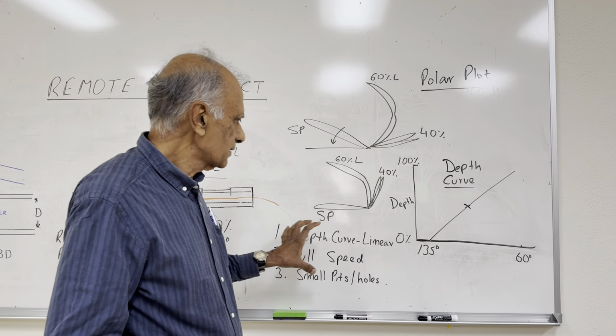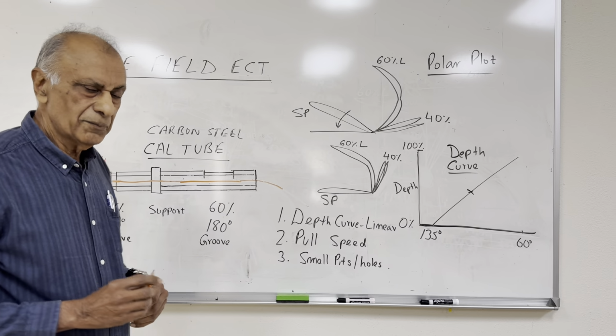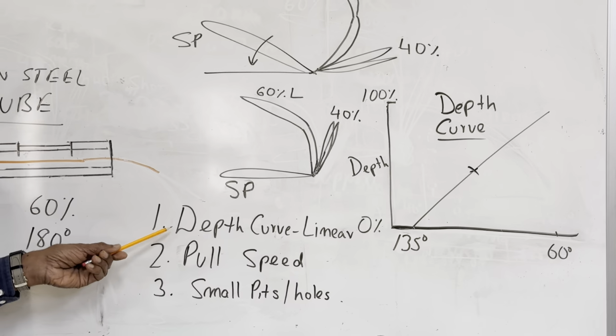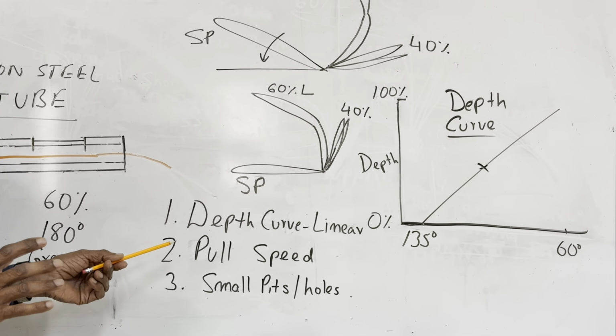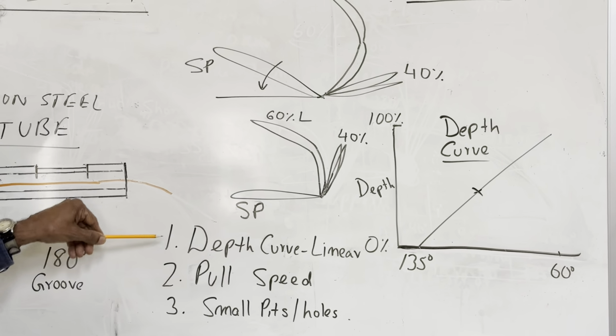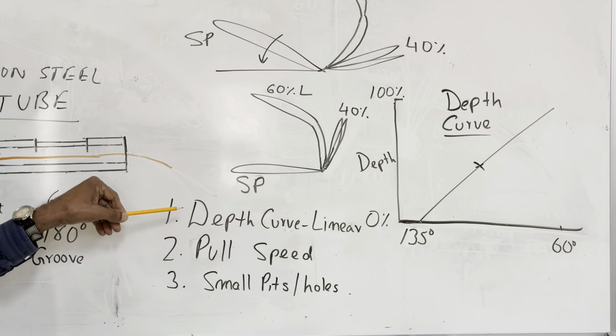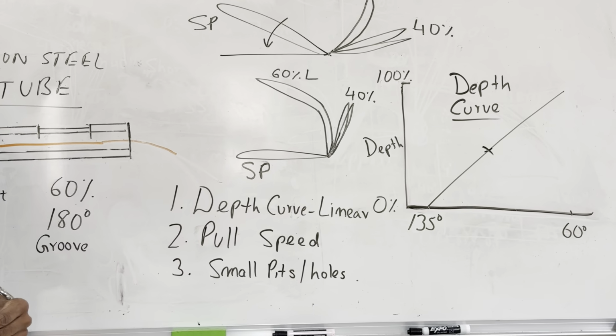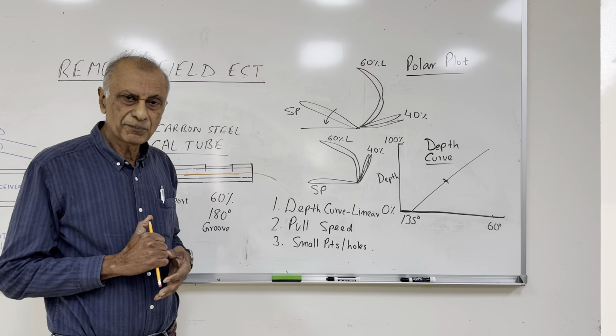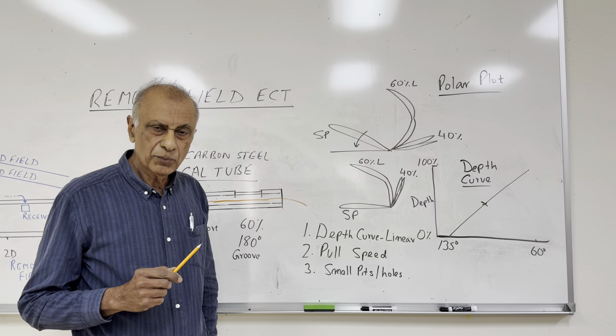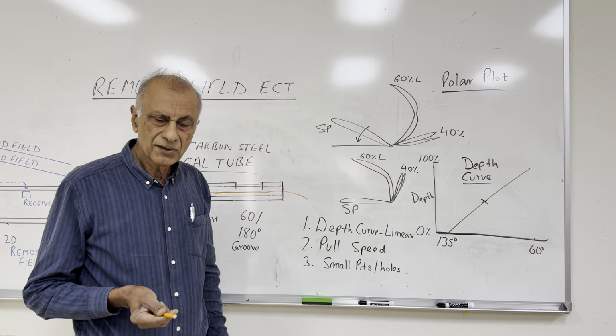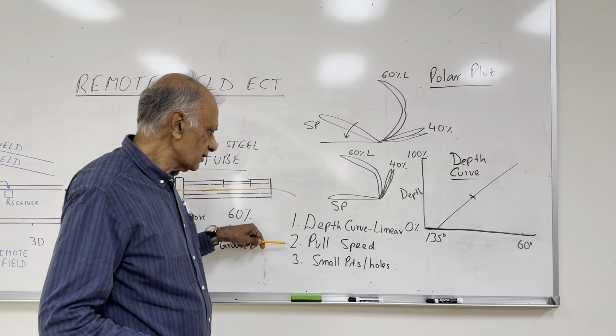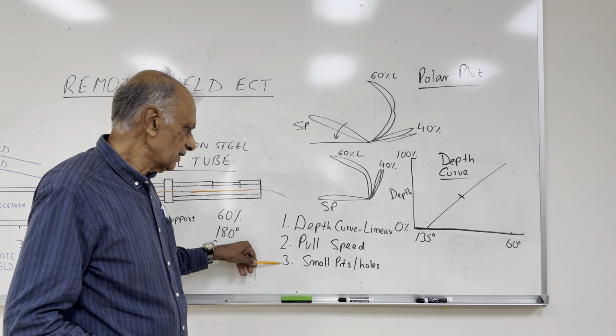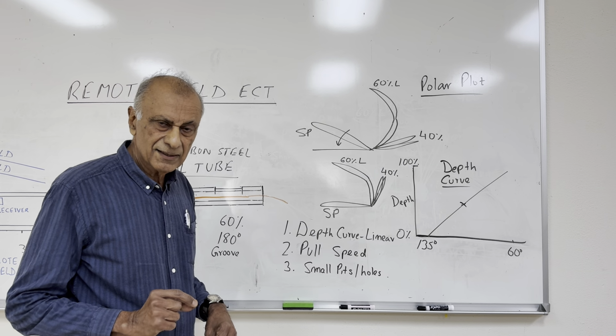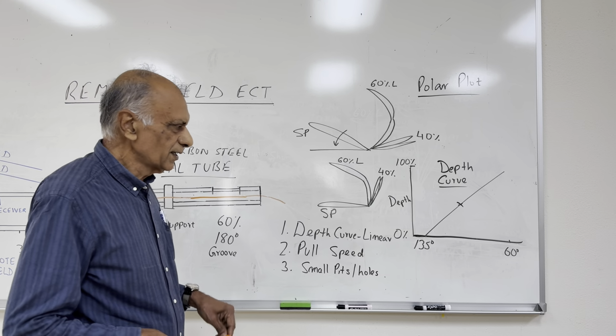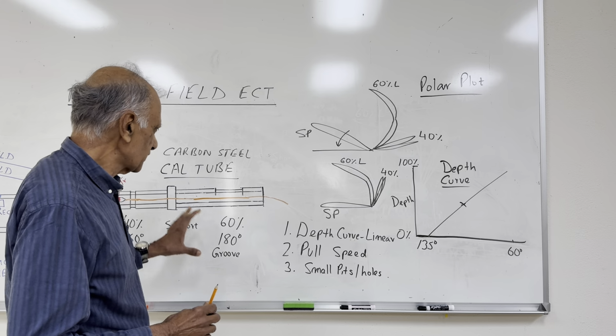So now, just to give you some limitations and some highlights about the remote field. First of all, the remote field is linear. The phase delay is linear, and this is different than the conventional eddy current. So the depth curve and the phase delay for the remote field is linear. And then also the pull speed for remote field is slow. As compared to conventional eddy current, where we can pull probes at 1.5 meters per second, here we are just going to be pulling at about 300 millimeters per second, or 1 foot per second. So pull speed is slow as compared to conventional eddy current, and it's not a good technique for detection of small pits and small pinholes, so it will most likely miss them. It's basically a good technique for wall loss measurement, and that's what it should be used for.